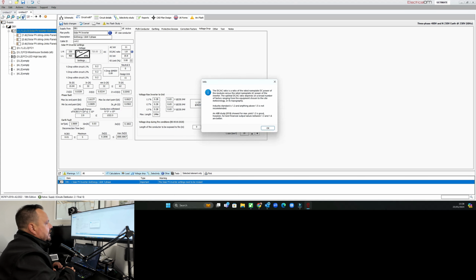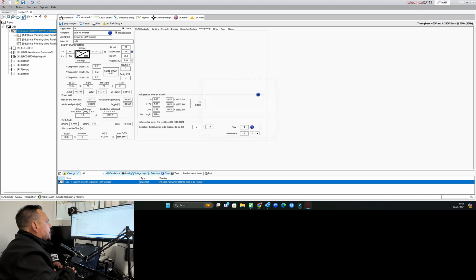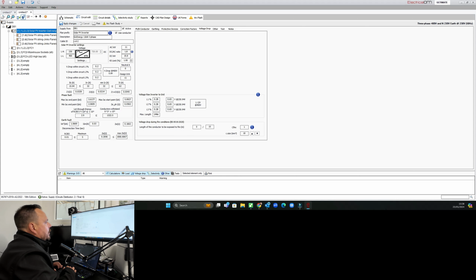If we click that box here, it tells you what industry standard is. So our oversizing is probably a little bit high in this circumstance, but it is what it is just from using the preset values. Again, you can adjust your volt drop limit. If you want to come down to 2% or even 1%, you can do that. And then any warnings would apply to the circuit based upon that design. It depends how strict you want to be with that.